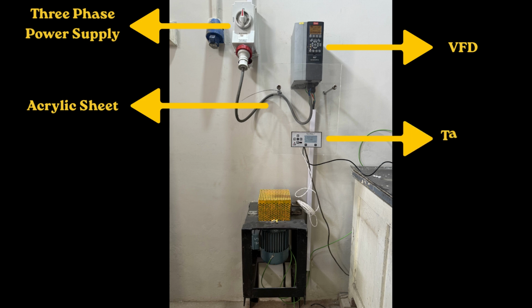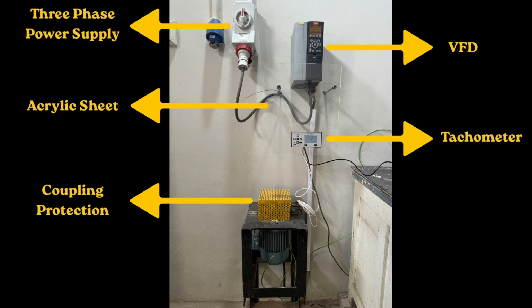The tachometer unit receives signals from the speed probe and converts them into RPM readings. The coupling protection ensures operator safety by preventing accidental contact with rotating parts. The speed probe detects the rotation of the shaft or coupling and sends the pulses to the tachometer. The motor acts as the rotating element of the setup, similar to the rotating machinery in industrial plants.